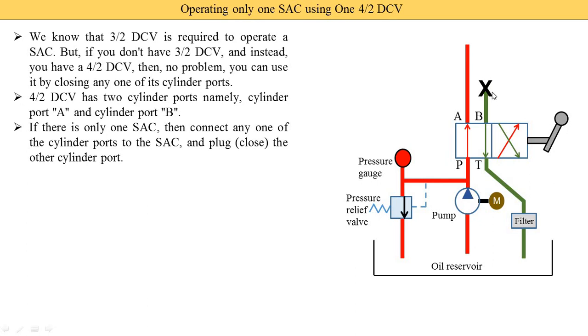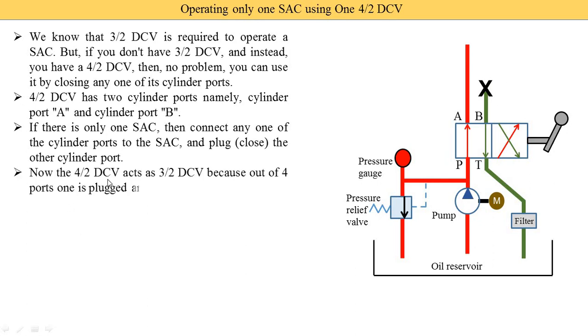You can also block port A — it depends on you. It is not necessary to always block port B. Now the 4/2 DCV acts as a 3/2 DCV. Why? Because out of 4 ports, one is plugged — plugged means we block it — and only three remain open. The B port is blocked, so we have only three open ports: A, P, and T. So this 4/2 directional control valve works as a 3/2 directional control valve.